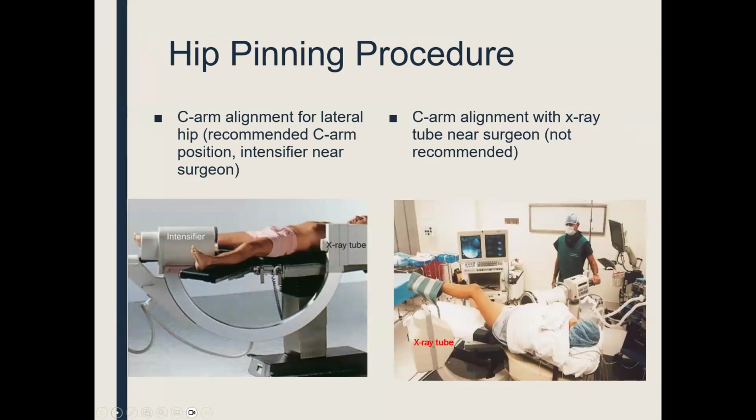I would highly suggest when you get into your clinical environment where you have C-arms, even if you do now, take the time to go and manipulate the C-arm. You need to learn how the locks work, how to rotate it, how to push it in and out, how to save the image, save the last image on the monitor. You really need to know how to do all those things. It's not the time to learn when you're in the middle of a surgical procedure, okay?